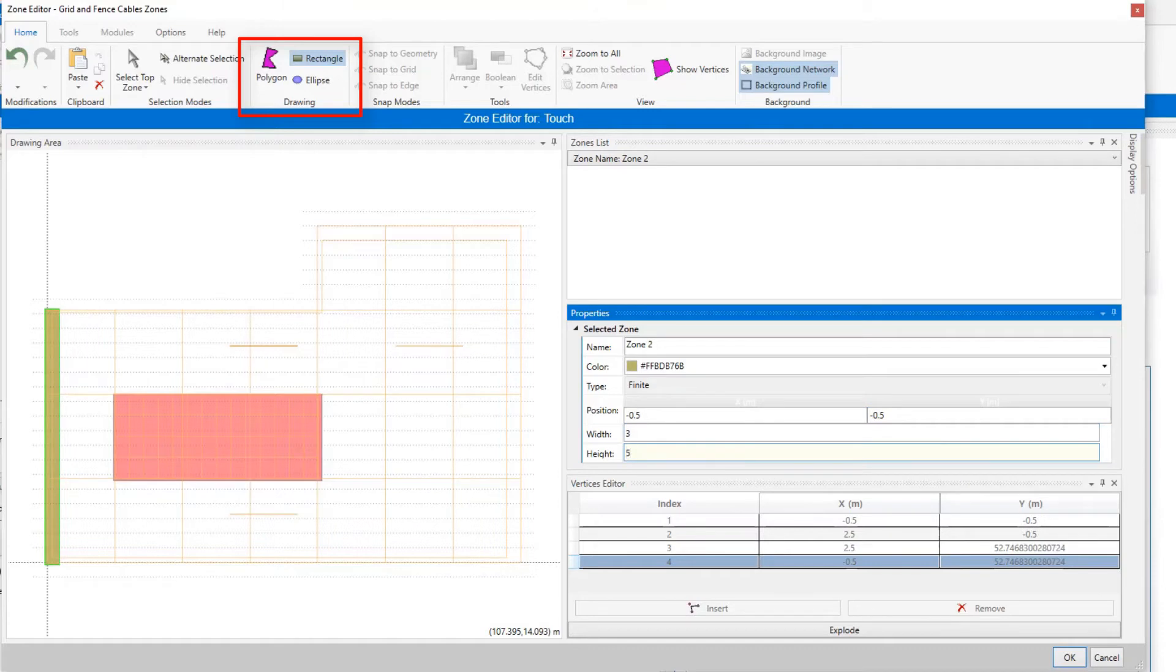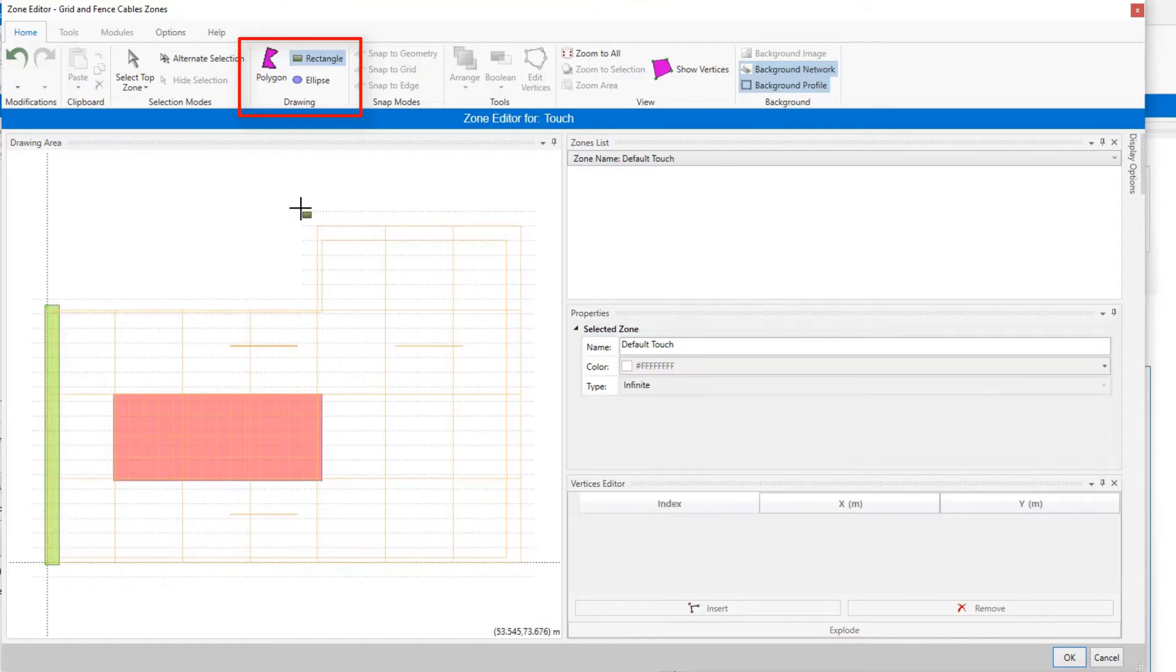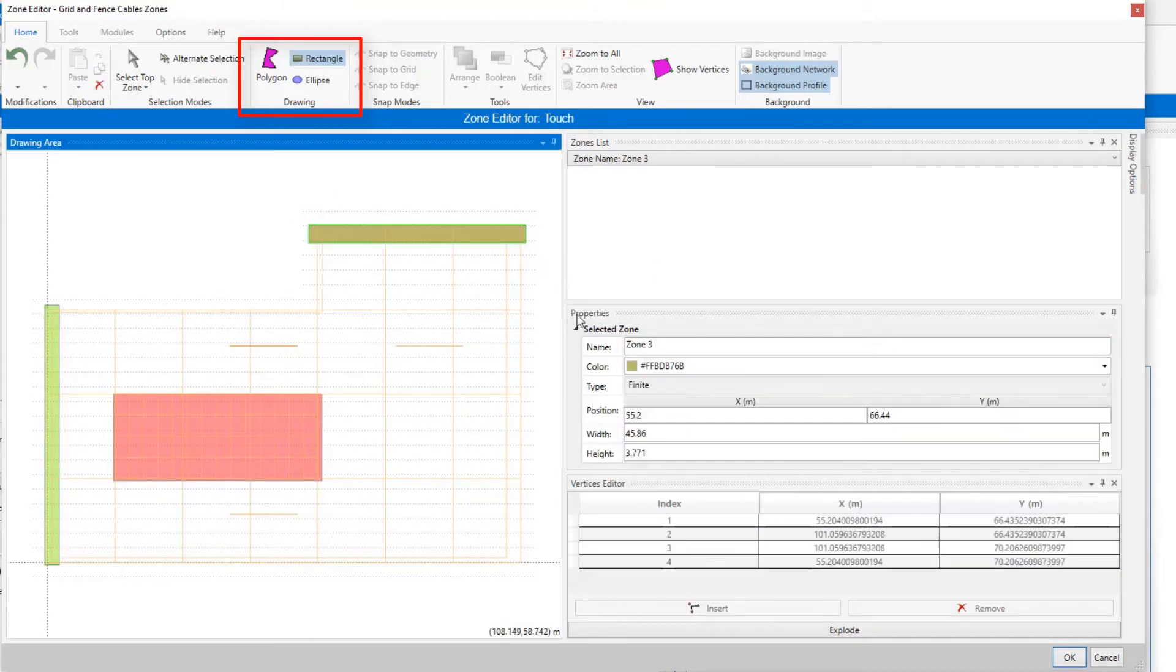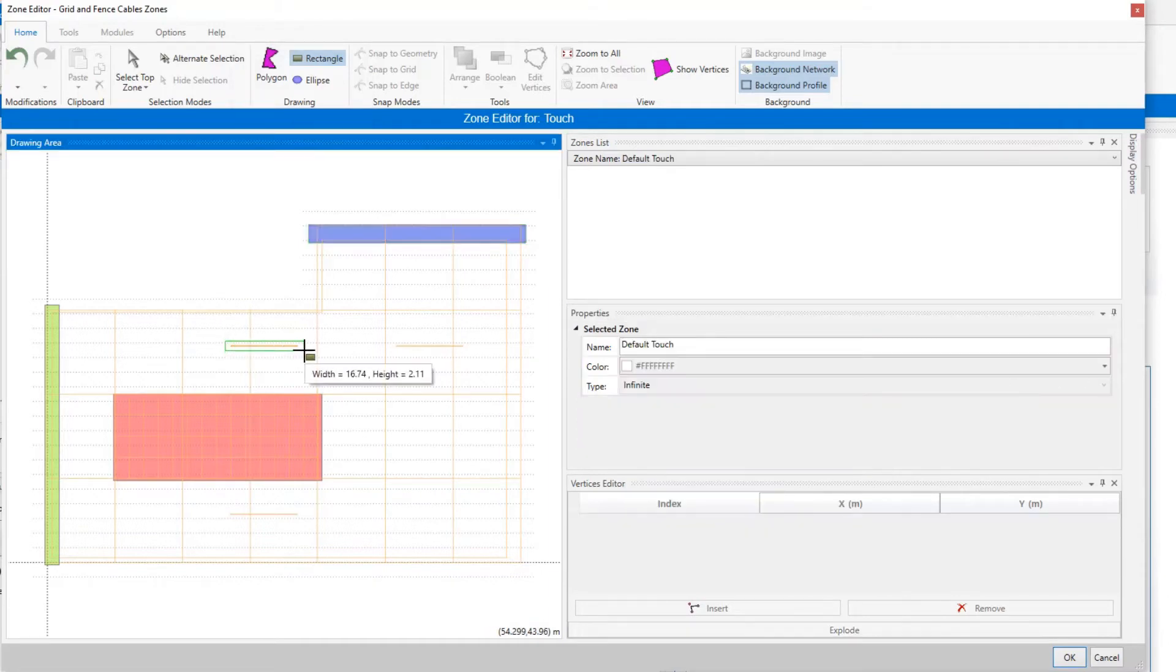Then in the left area of the substation, we want to examine the touch voltage near the fence. And in the top area, we want to assess the step voltage, so we define specific zones accordingly. You can add as many zones as you need according to the safety requirements of your project.